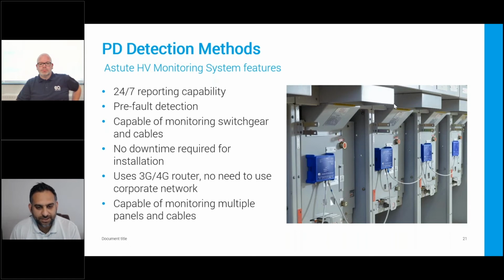If you've gone through a large asset base, then you will come to a situation where you've identified some PD on some of your critical assets, and for whatever reason, whether that's operational or budgetary, you can't do any remedial actions. You would want to monitor that partial discharge activity and trend it to see if it's going to increase over time. And that's where continuous monitoring, or as we call it, the Astute HV monitoring, comes into play.